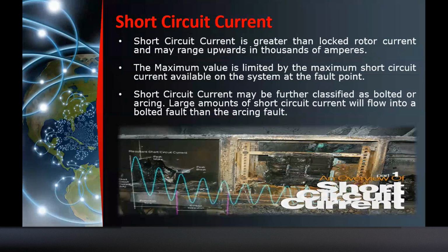Okay? Short circuit current, the maximum value is limited by the maximum short circuit current available on the system at the fault point. Short circuit current may be further classified as bolted or arcing. Large amounts of short circuit current will flow into the bolted fault than the arcing. So pag bolted, usually class, mas malaki sa arcing. Because pag nagkaroon ka na ng arcing, meron ng impedance of air. Diba? Kaya nga, kung mapapansin nyo, pag nag-conduct kayo ng arc flash analysis, pag in-input niyo yung bolted fault or your three-phase fault dun sa formula ni arc flash, bumababa yung arcing current mo because of that air. Okay?